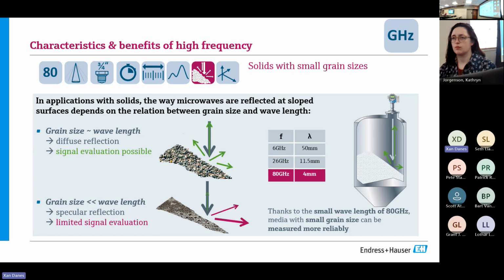The non-contact measurements in solids have always been a challenge. With lower frequency radars, you had a wider wavelength and didn't get a lot of signal back to the transmitter. With something like a laser, you might be able to measure the solid level when you can physically see it, but certain measurements really struggle with dust, like laser and ultrasonic, where the dust can attenuate that signal.